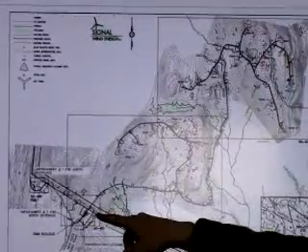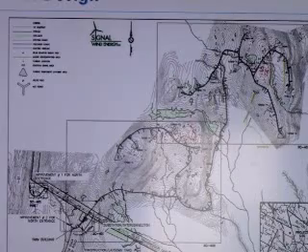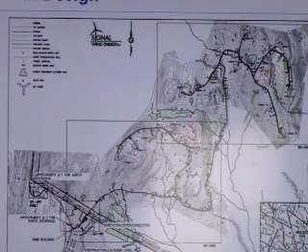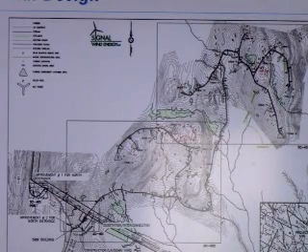The power is then stepped up to 115 kilovolts, and that's what goes out on the transmission line into the ISO New England grid. So what is the size of the underground transmission? 34.5. And how many of those do you have? 16 turbines, but just one 34.5. Well, there's two collectors. What we call our two collector circuits or two runs.